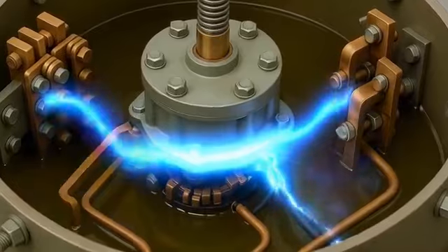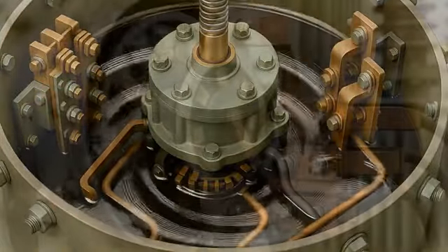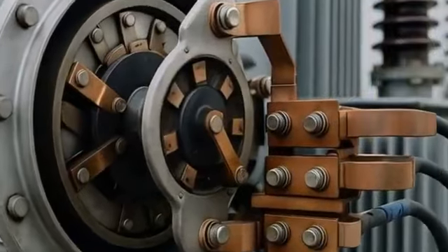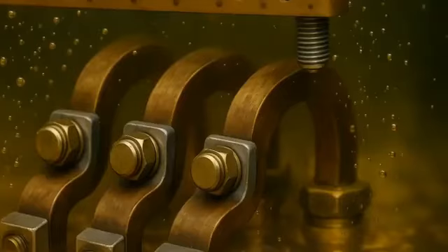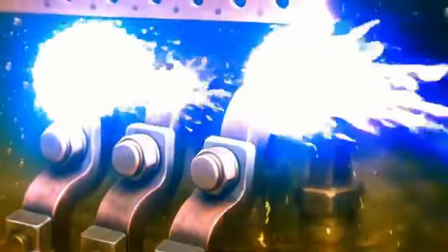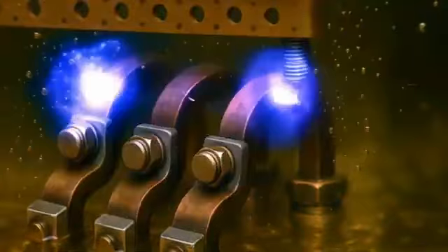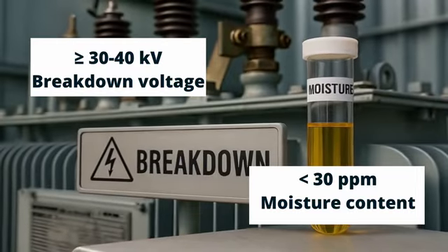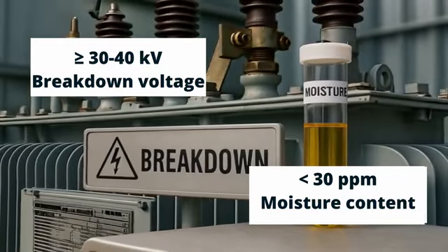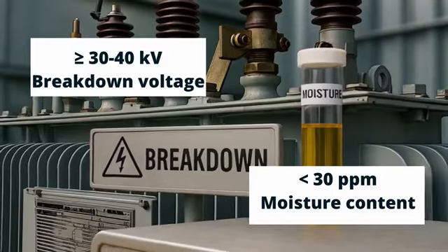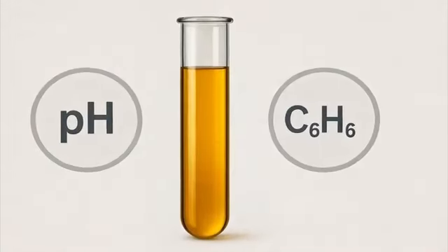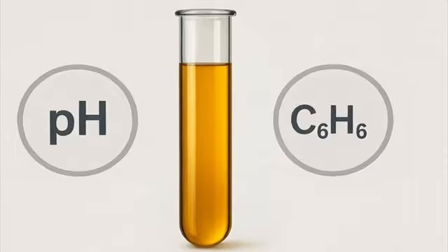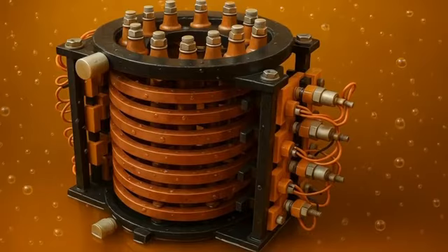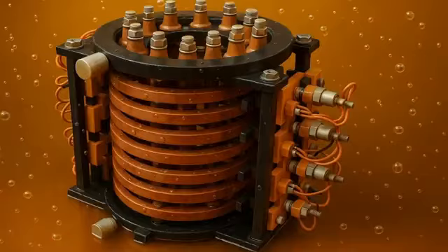Recurrent arcing degrades the oil. The situation is also aggravated by the contacts heating up, which rate rises with an increase in transition resistance. In order to ensure that onload tap changer oil performs its functions properly, its breakdown voltage shall be at least 30 to 40 kV and its moisture content shall not exceed 30 parts per million. Other onload tap changer oil characteristics, color, acidity, carbon content, are less critical and do not affect the possibility of using an arc quenching medium in the contactor tank.